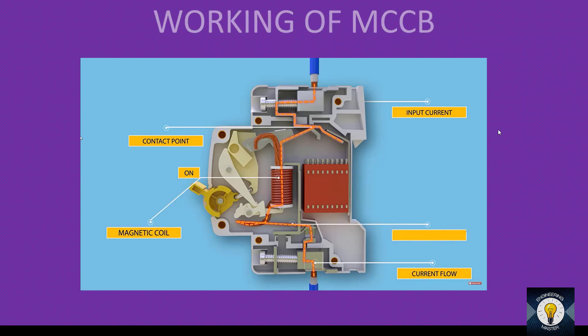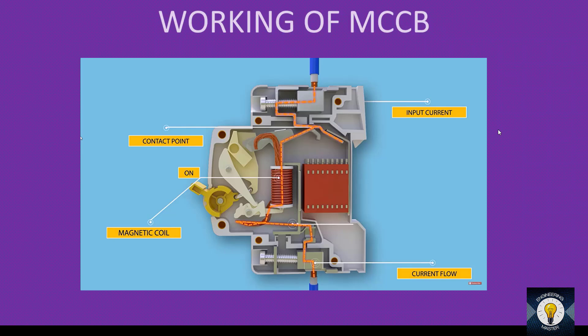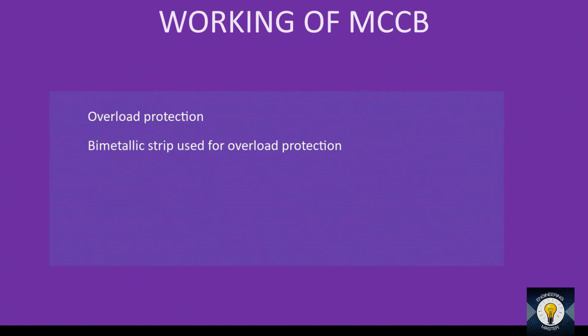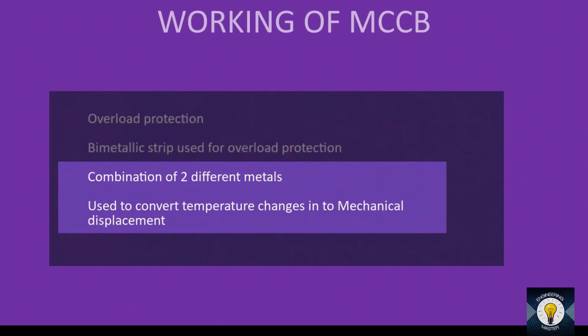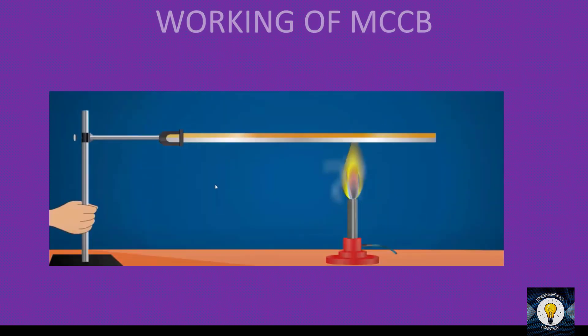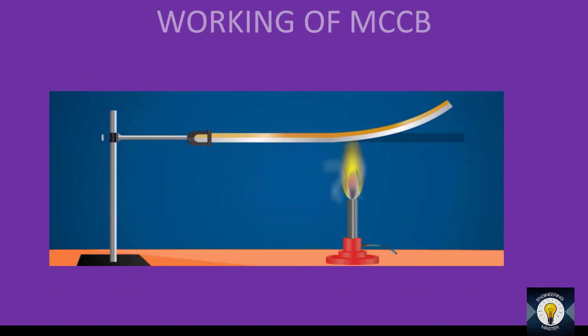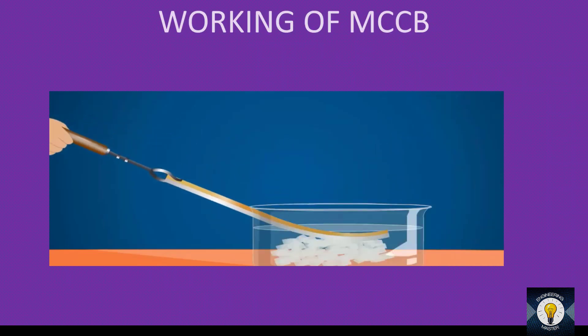If a short circuit happens, the current increases by a huge amount — there is a sudden surge of current. The magnetic trip unit is used to trip the MCCB. The bimetallic strip is used for overload tripping. The bimetallic strip is a combination of two metals used to convert temperature changes into mechanical displacement. While heating, the bimetallic strip bends; if the temperature returns to normal, the bimetallic strip comes back to the same position.